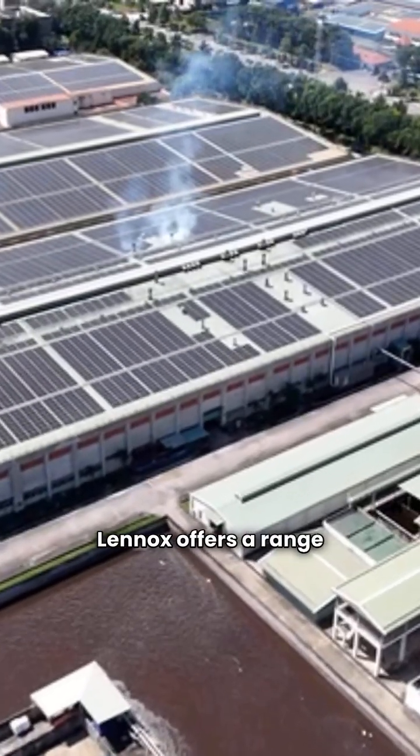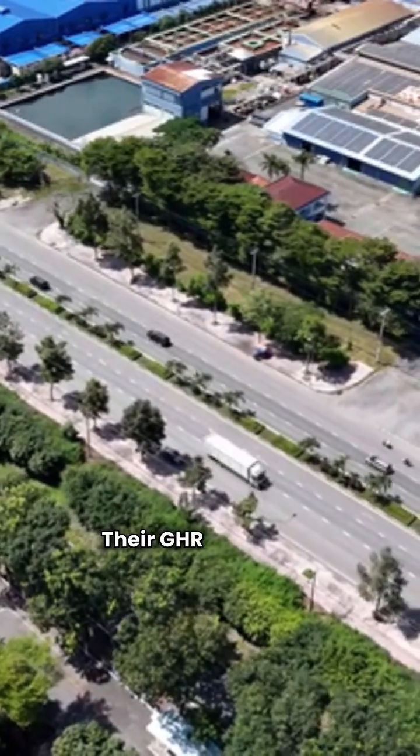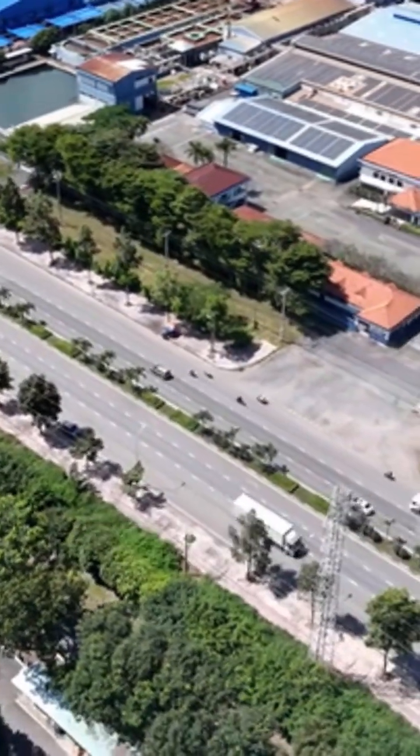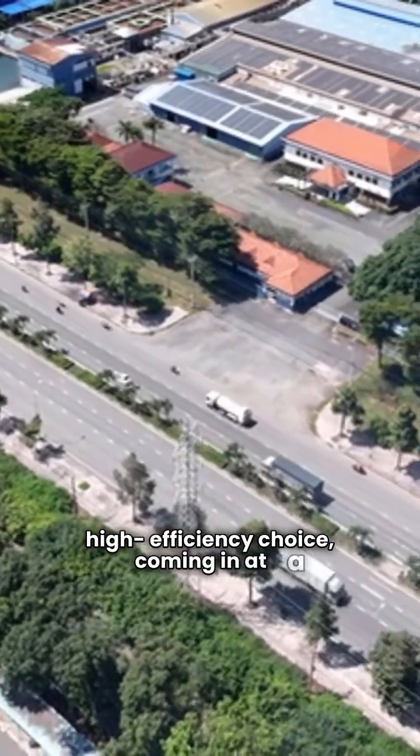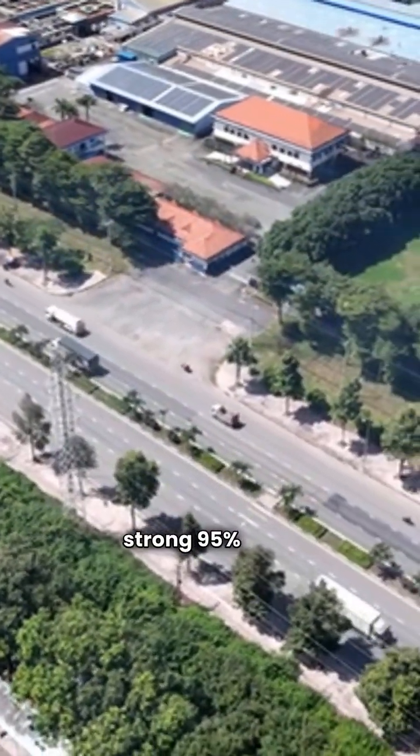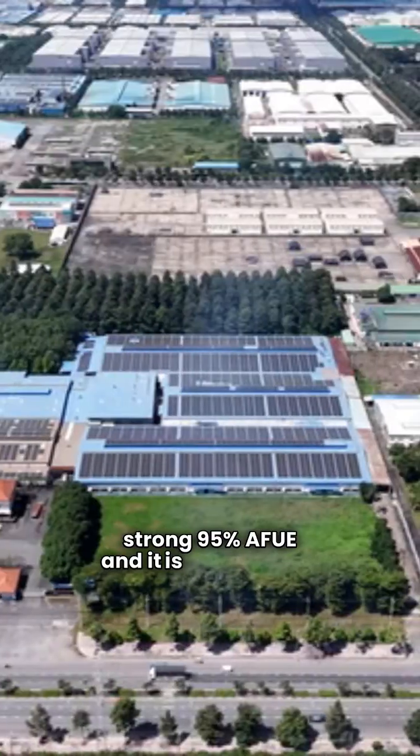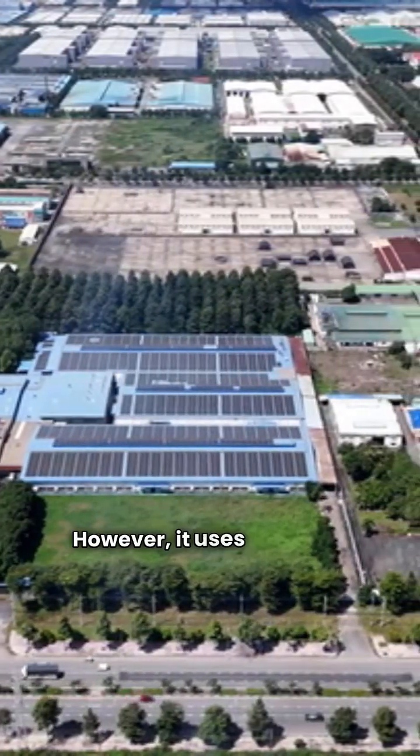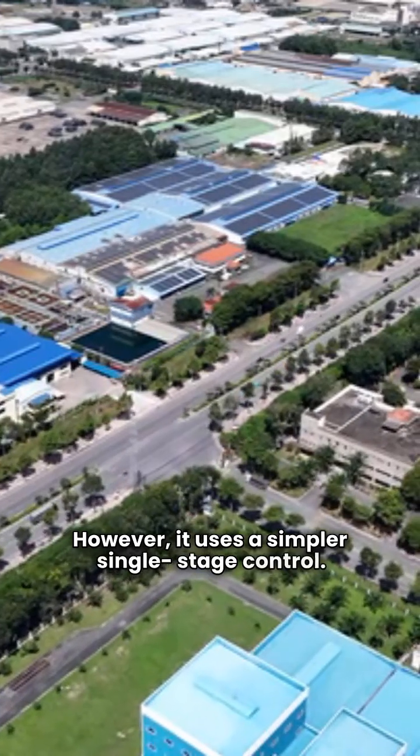Now for Lennox. Lennox offers a range of models. Their GHR gas water boiler is their high efficiency choice, coming in at a strong 95% AFUE, and it is condensing. However, it uses a simpler single-stage control.